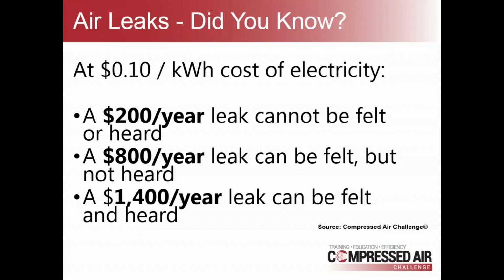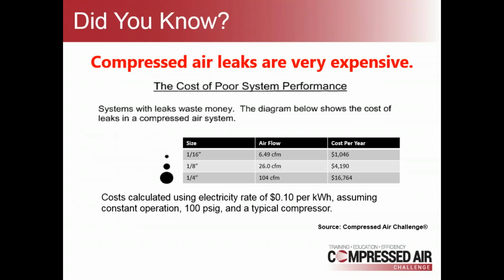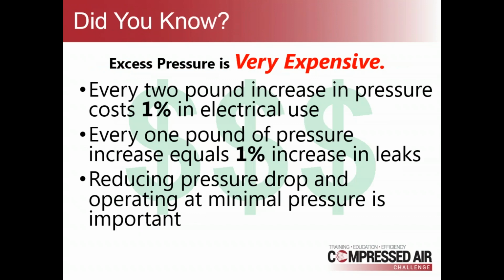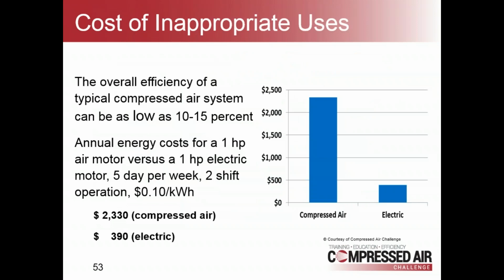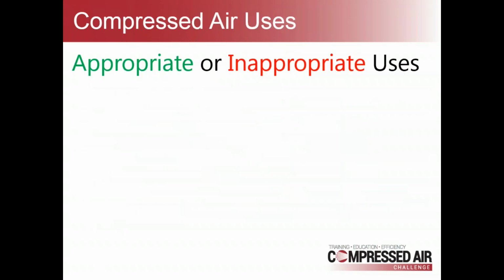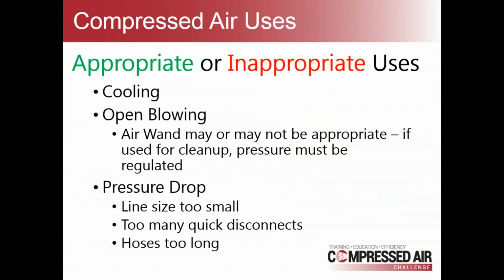This can also be adjusted for the actual cost that they have, as well as this chart. This chart is customizable. It's done at 10 cents a kilowatt hour, but guess what? It can be changed for whatever the cost is. Then letting them know it's very expensive. So we talk about the 2 PSI equals 1%, and then the increase in leaks, and then reducing pressure drop is important. The overall efficiency of the system, which you saw in this slide before, and whether it's inappropriate or appropriate.